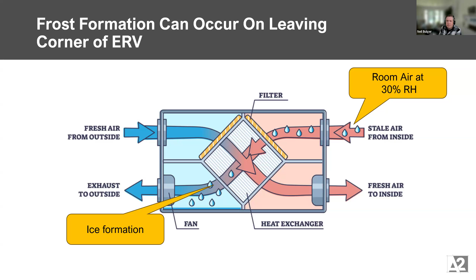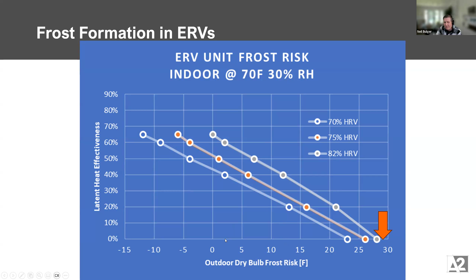Here are some charts of where frost would occur, using basic relationships on energy recovery—showing latent heat recovery effectiveness and at what point frost would form on the coil. For an HRV, if you had 30% moisture inside your building, you'd potentially get frost risk at 28 degrees. With about 40% latent recovery, that drops to 12 degrees outside air, and at 60% recovery, you're down to about 2 degrees outside air.